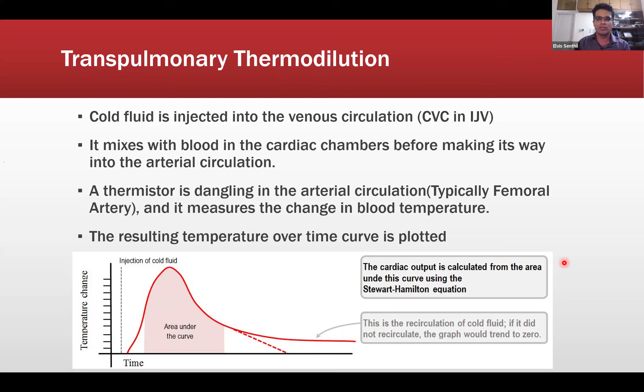So instead what we do is we inject cold saline once or twice or thrice, and then we calculate the cardiac output. And then using that, we calibrate the pulse wave analysis, and we use the pulse wave analysis to measure our cardiac output continuously. Now this cold fluid is injected intermittently to calibrate it alone. Now this calibration occurs once every 8 hours or so, or if there is a major change or you're having some questions about the values.